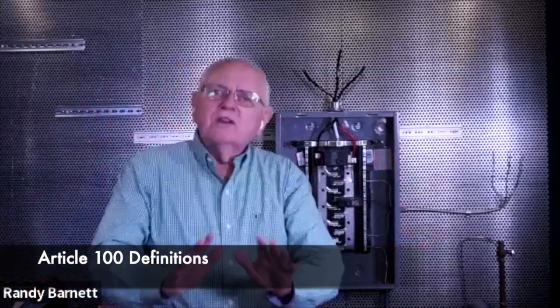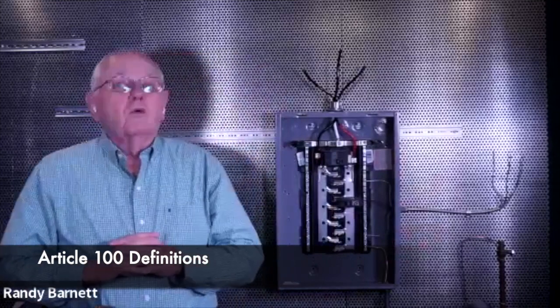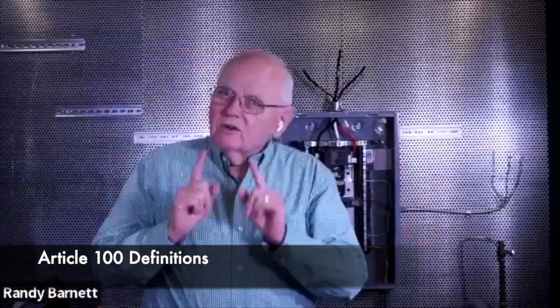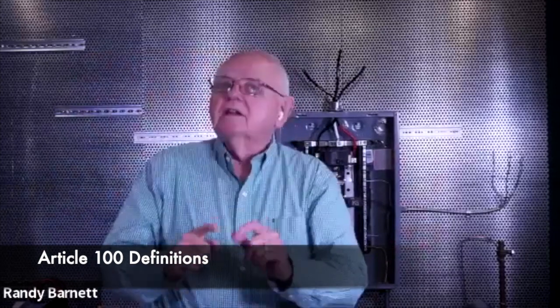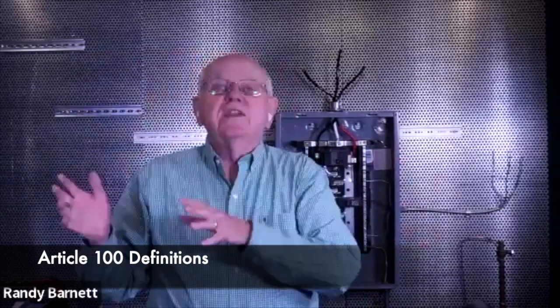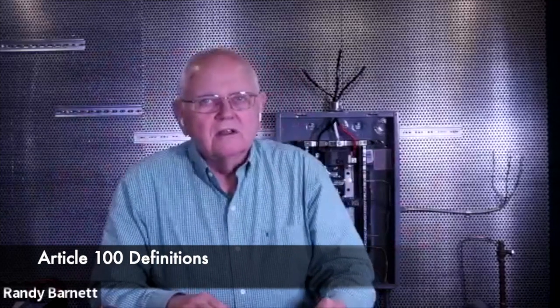If we're going to comply with the NEC, if we're going to read and interpret the NEC, if we're going to be able to talk turkey with people, we all need to be on the same page. And so we need to go to Article 100 of the NEC. I've got the 2023 NEC in front of me today. Article 100 is on definitions. If you haven't looked at the 2023 NEC yet, you're going to notice that all the definitions have been moved up to Article 100 now. So go to Article 100, or if you're using a previous edition, go back and take a look at some of the different articles where those definitions may be, usually in the .2 section.